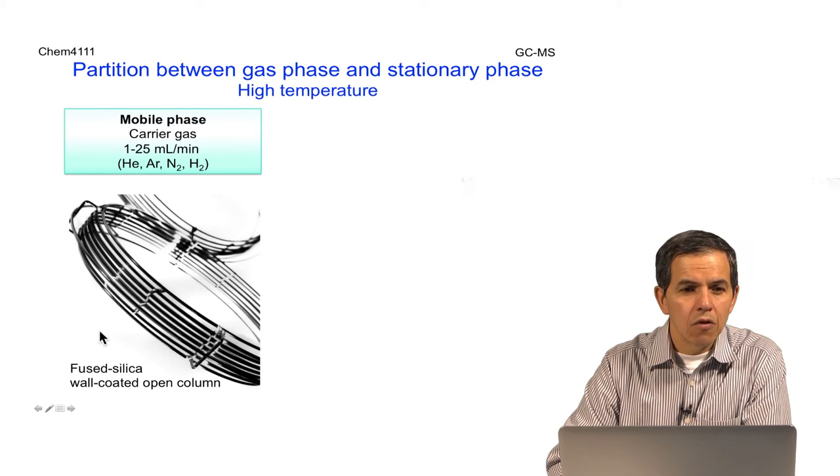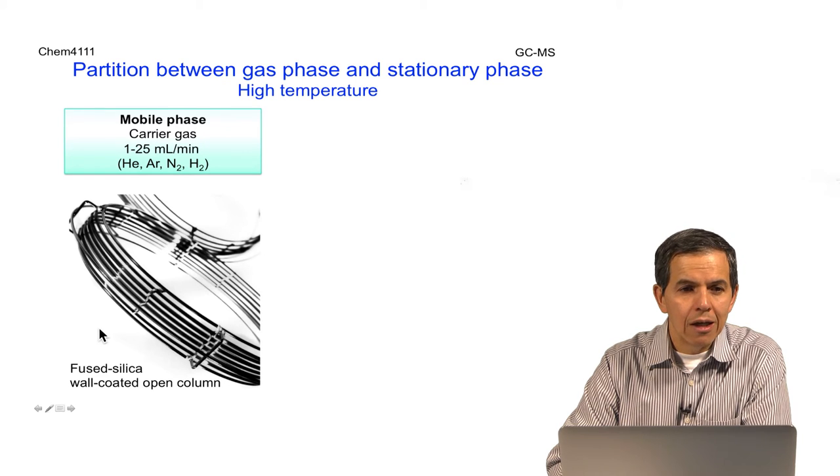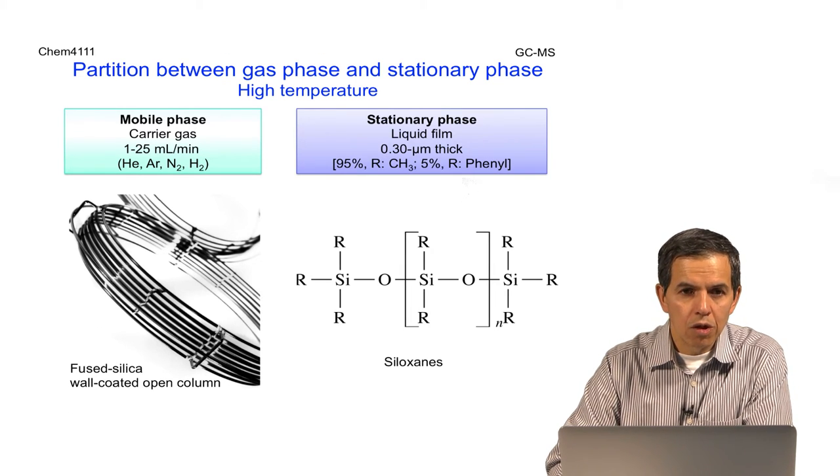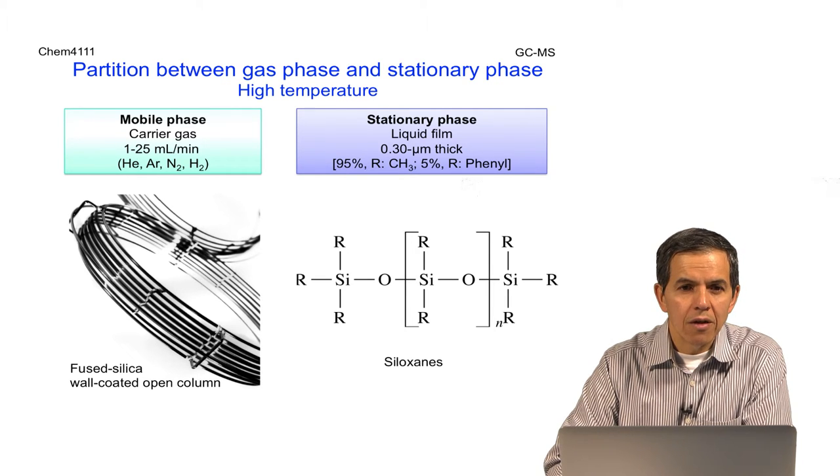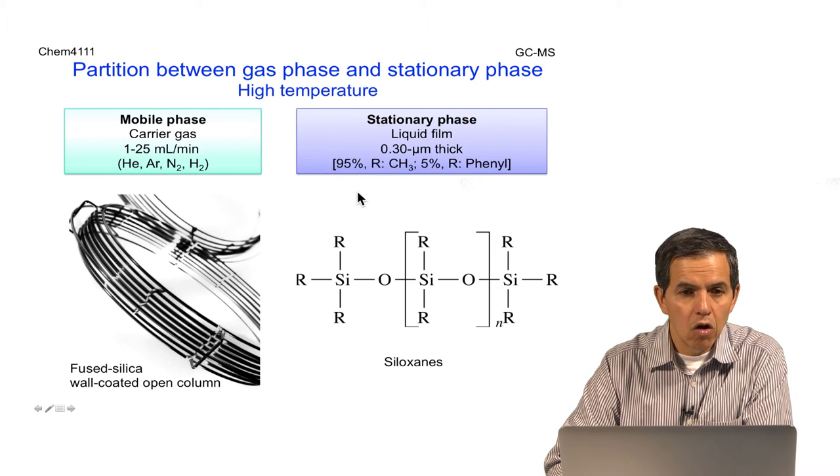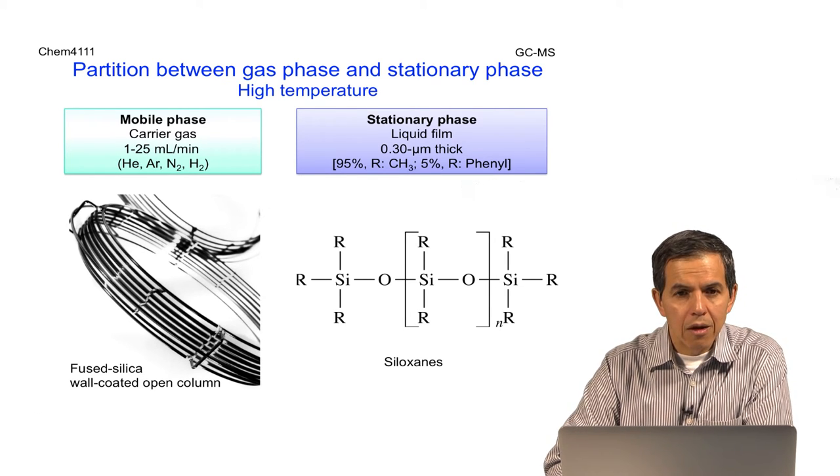The column is made out of fused silica, is open, and right in the inner wall there is the second component, which is the stationary phase. The stationary phase is usually polymeric in nature, but still in liquid form. This thin layer that coats the inner component of the column provides the ability to partition compounds between the gas phase and the stationary phase of the column.